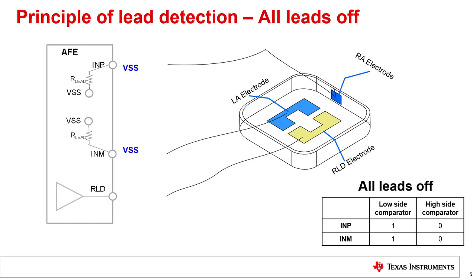To understand how DC lead detection works to distinguish between the three configurations, we will start with the case where all leads are off. Consider the case of resistor biasing the leads, where the bias resistor R-lead biases both INP and INM to VSS or ground. Since the leads are open and there is no other mechanism to set the bias on the pins, the voltages at the INP and INM pins are solely determined by the lead bias potential. Therefore, the voltage at both INP and INM pins is equal to 0 volts. By setting the high and low threshold voltages for the comparators to voltages within the range of VDD and VSS, a leads-off condition of both INP and INM leads can be determined.